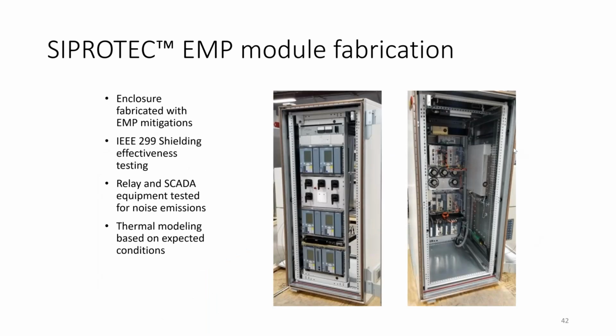So when we began going from concept to fabrication, we knew that we wanted to address all of the electromagnetic threats. That would be HEMP, IEMI, and GMD or GIC. We wanted to capture all of that within one module, but we also wanted it to be a consistent set of hardware so that it would be scalable and repeatable. Once we had the hardware established, we could replicate it across our system with greater ease instead of having to do custom fabrication for each project. So what you see here is the finished module that's been fabricated. It's roughly a 4 foot by 4 foot footprint that fits inside of our existing control house.